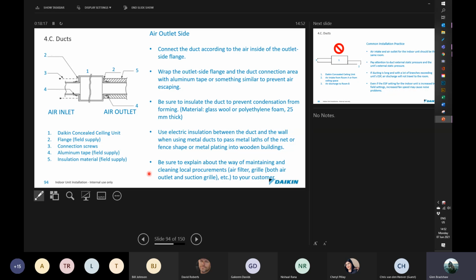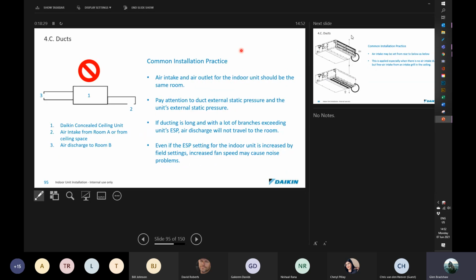So when you hand over the job, these are the things you need to make your customer aware of: where the service access to the unit is, where you get access to the filters, and those types of things. Something else to remember, very briefly, is that the return air and discharge are in the same room. They should never be in separate rooms, as that's going to negatively influence the performance of the unit. Pay attention to the duct external static pressure and the unit's external static pressure.